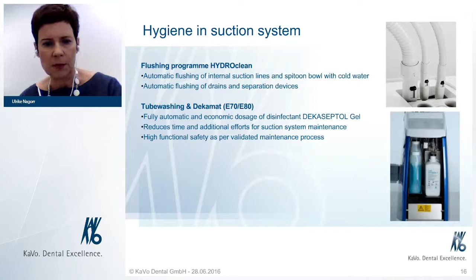You can maybe a little bit hear it. It's the so-called Aqua Mod. Once you take out, or your assistant is taking out, a suction tubing, an automatic flushing or rinsing of the selective valves inside the suction systems starts. That means permanently a certain dosage of only cold water is given into the suction system when the suction itself is active.